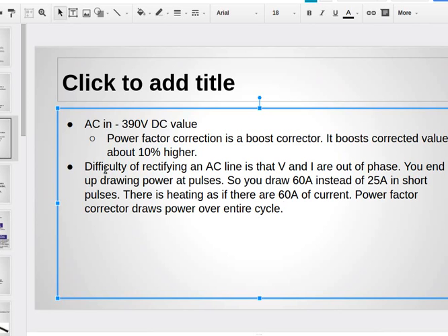You pulse width modulate the line current. And it steps it up. When the line voltage is quite low, let's say 20 or 30 volts, during that part of the sine cycle, it's stepping that up to 390 or so, and feeding that to the filter capacitor.